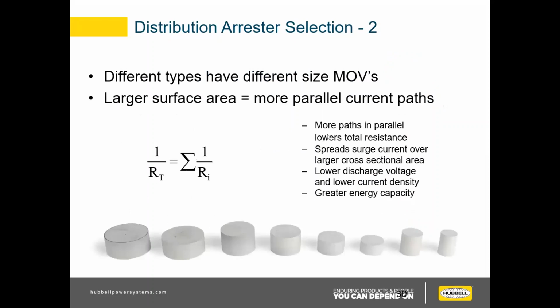So a little more about MOV blocks. Our different types will have different size MOVs. And like I said, with a larger surface area or larger diameter, you can handle more energy due to more parallel current paths. It's kind of like a water hose: more paths in parallel lowers resistance, and it'll spread the surge current over a larger cross-sectional area. That in turn will lower your discharge voltage and your current density, and like I said, gives greater energy handling capability. This is a good lineup for all of our arresters, ranging from about 29 millimeters to 75 millimeters.